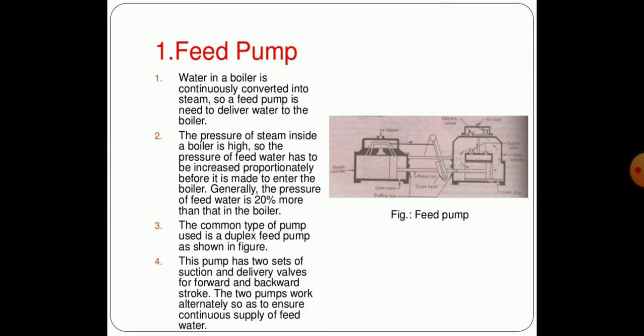Now we can see all these functions one by one. First one is feed pump. Water in the boiler is continuously converted into steam, so the feed pump is needed to drive water to the boiler. The pressure of steam inside the boiler is high, so the pressure of the feed water has to be increased proportionally before it enters into the boiler. Generally the pressure of feed water is 20% more as compared to the boiler pressure. A common type of pump used is the duplex feed pump as shown in figure. These pumps have two sets of suction and delivery valves for forward and backward strokes. The two pumps work alternately so as to ensure continuous supply of feed water.